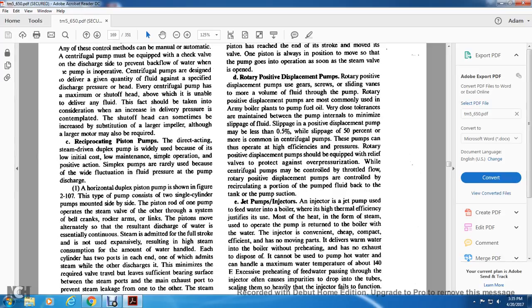Rotary positive displacement pumps. Rotary positive displacement pumps use gears, screws, and sliding vanes to move fluid from the pump. They are most commonly used in Army boiler plants to pump fuel oil. Very close tolerances are maintained between the pump internals to minimize slippage of fluid. Slippage in a positive displacement pump may be less than 0.5 percent, compared to a slippage of 50 percent in the most common centrifugal pump. These pumps can also operate with high efficiency at high pressure.